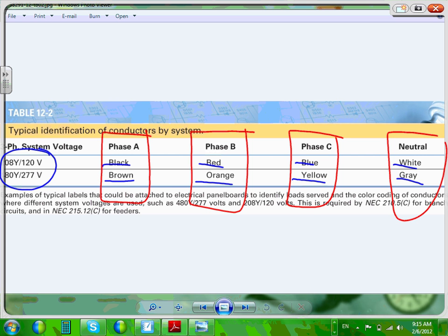When I say by phase, phase A is different from phase B for the 208, from phase C, and from the neutral. Neutral is always different. That's no question asked. But also system by system. Phase A in system 1 is different color-wise than phase B in system 2. And by the way, this applies for branch circuits and feeders. Can I get you guys to remember that? This is only required if you have two systems or more. If you have one system, you can use brown color for phase A, phase B, phase C, and white for the neutral, and that's legit.